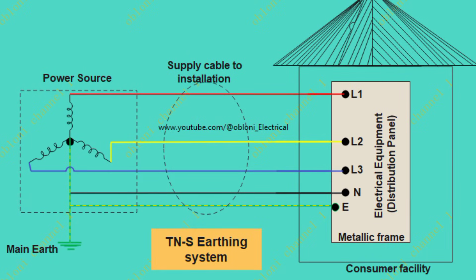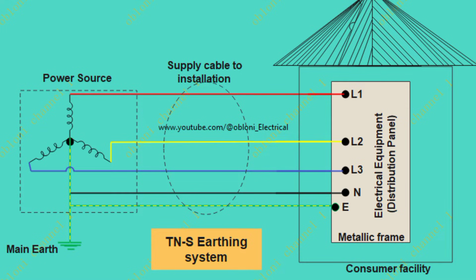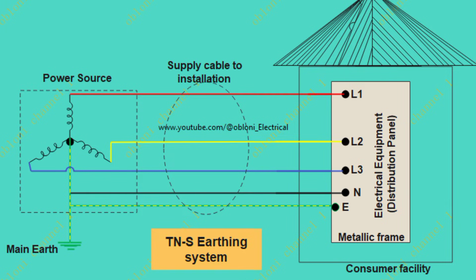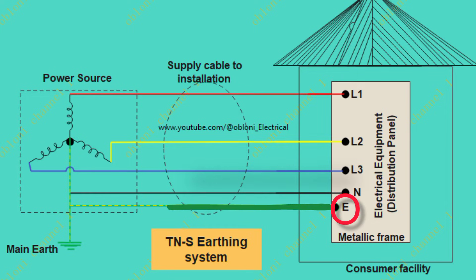In the TNS earthing system, the neutral conductor and the protective earthing conductor are separate conductors throughout the entire installation. If the earthing system provided by the power distribution authority is a TNS system, this means that you will have five wires supplied to your house: L1, L2, L3, neutral, and protective earthing. For a single-phase supply, you will have three supply cables: live, neutral, and earth. In this system, the consumer does not need to bury any earth rod for the installation — you just have to connect your earthing system to the main earth provided by the supply authority.